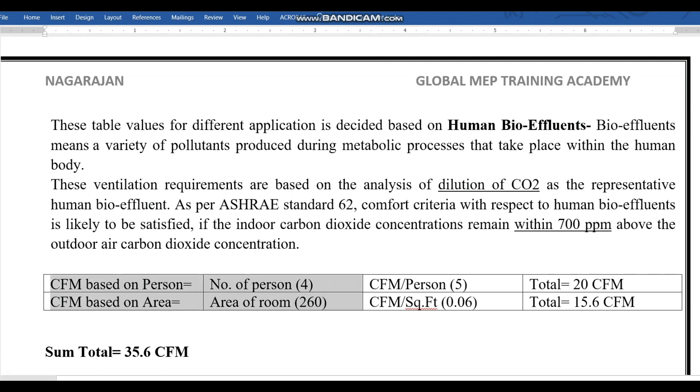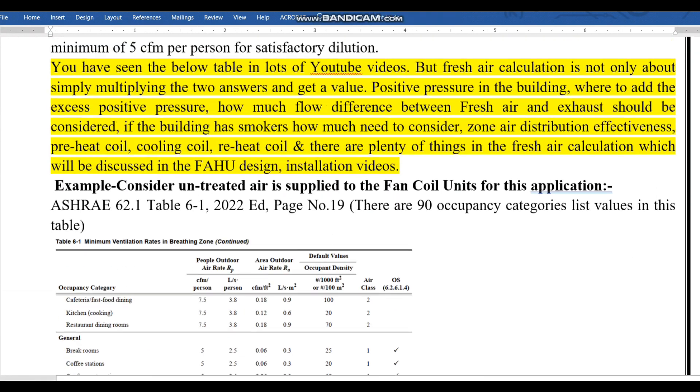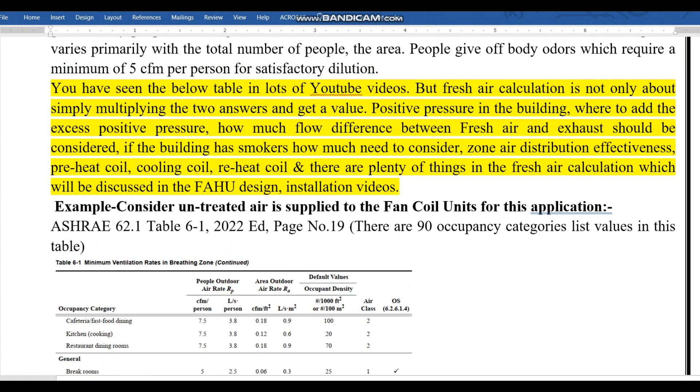As far as I am concerned, fresh air is not only this one table. For small rooms it's okay, but when it comes to practical design engineering there are plenty of things to consider. For example, we have to maintain the positive pressure in the building, so where to add the excessive pressure.